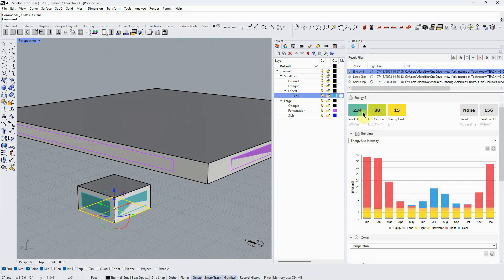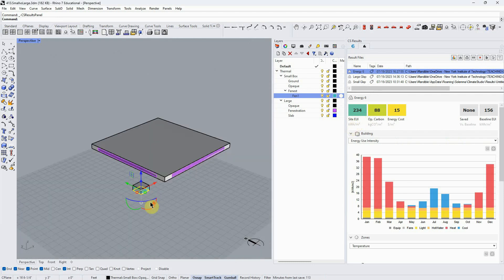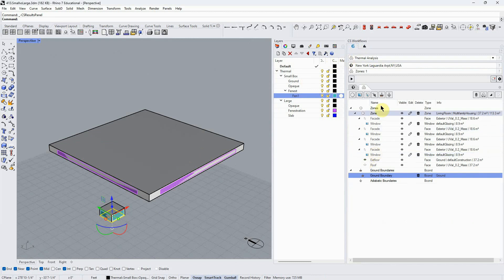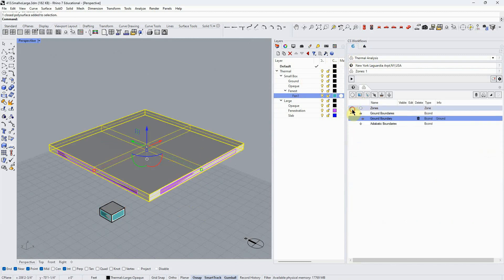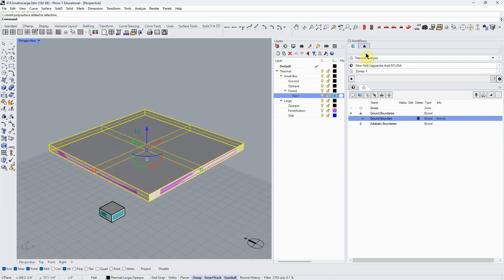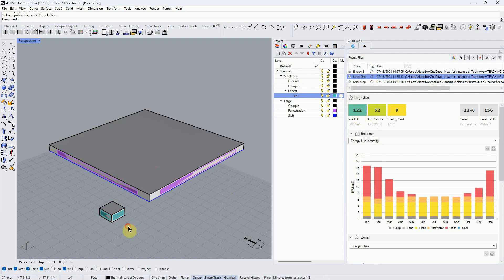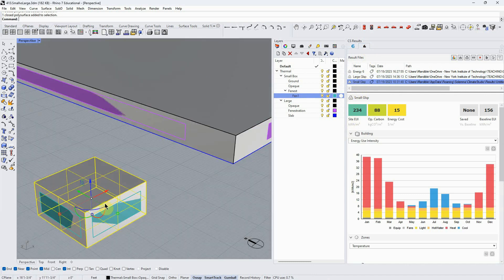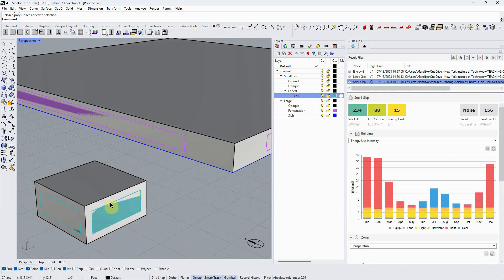Now I'm going to run it. So I see this is the output I get, and really all I'm interested in right now for the comparison is just showing how much energy we're using. The site EUI is 234 kilowatt hours per meter squared. Now if I wanted to run this again for this larger building, I'd have to delete these and select that zone. I've already run it to save time. The result was this: the large building has an EUI of 122, the small building 234—essentially twice as much energy per square foot of usable floor area in this one than in this one.